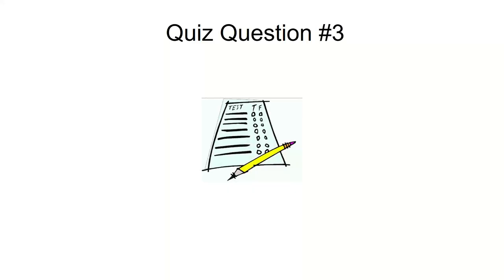All right, I'm closing this poll. The correct answer is in fact false. That sweet spot is 40 to 60%. You definitely do not want to be between 55 and 75. In fact, ASHRAE standards don't even want you above 60. Mold growth and bad things happen on there. So 75 is way too high.